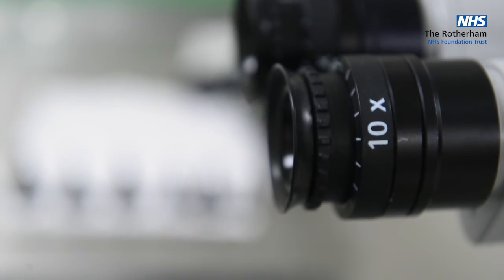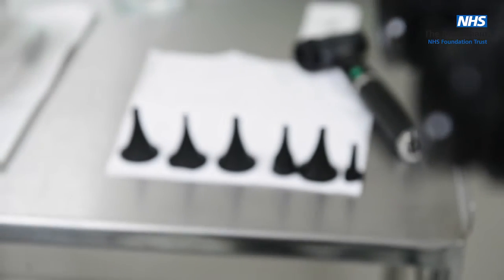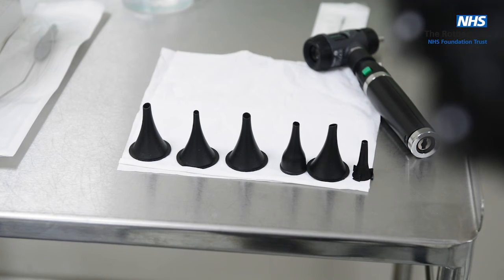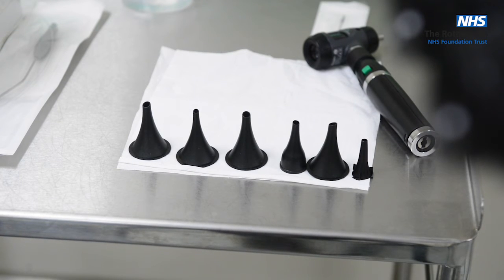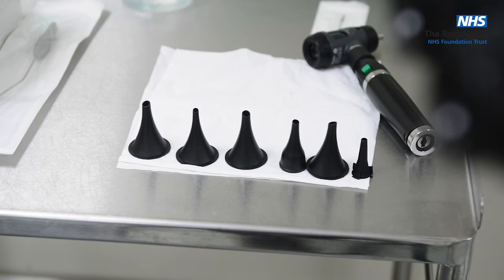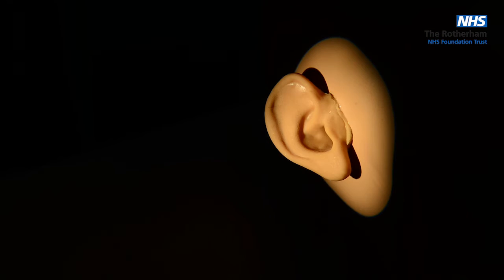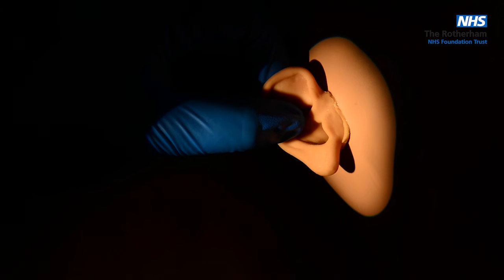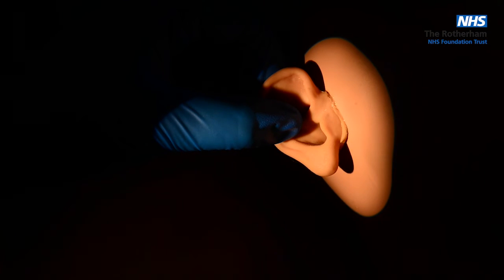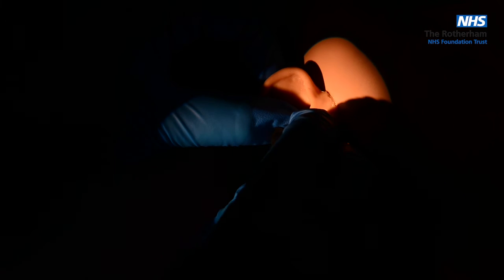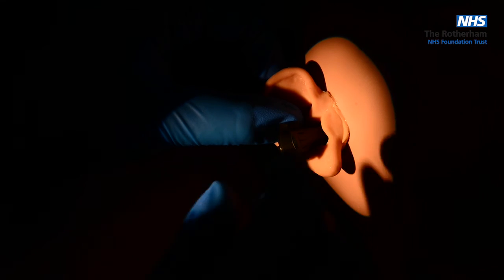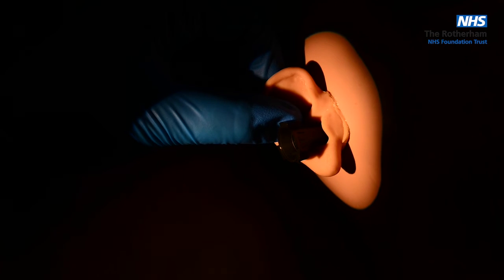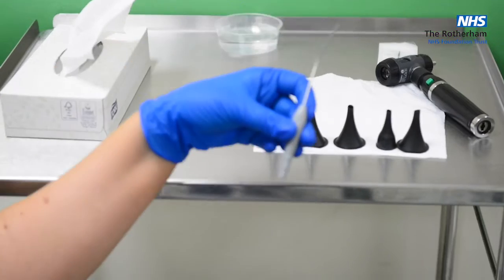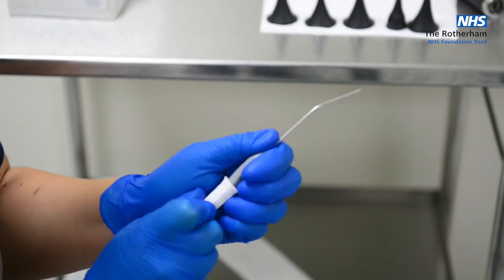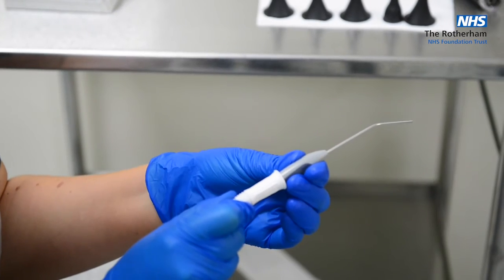Select the most suitable size speculi for the patient's ear. Various sizes are available, and the largest size should fit comfortably into the external auditory meatus. Gently pull the pinna upwards and outwards to straighten the external auditory meatus. Direct the microscope towards the ear and insert the speculum gently. Assess the patient's ear and decide upon the most appropriate size of suction tip. Insert the Zollner suction tube onto the suction connecting tube.